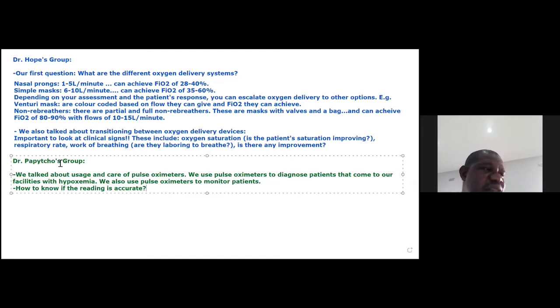We further discussed the types of pulse oximeters, where we said we have the conventional type and the reflector type. The conventional method uses two detectors, one which emits the light, and the other which detects the light that goes through either the finger where the pulse oximeter has been put, or the ear probe. Then we have the reflectors, which also have two detectors, one side emitting and the other side detecting. But with the reflectors, the emitting side reflects the light, which hits the bone and scatters the rays, which are then detected by the detecting side, and then it gives us the readings.